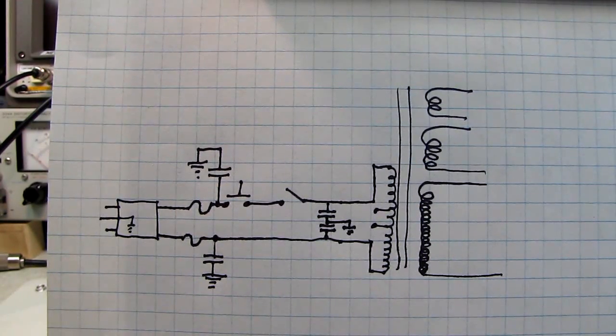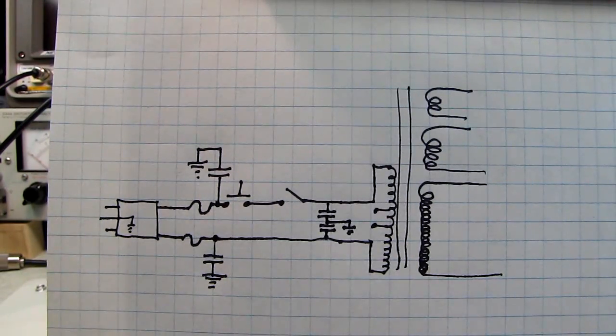So what we're going to do is move things around, pop the cover off of this, and see what we can find. And remember, inside of this, the voltages are highly, highly lethal. You've got a couple of thousand volts, actually close to 3,000 volts on the high voltage winding, and even under this configuration, you're still going to have 1,500 volts of AC on that secondary.